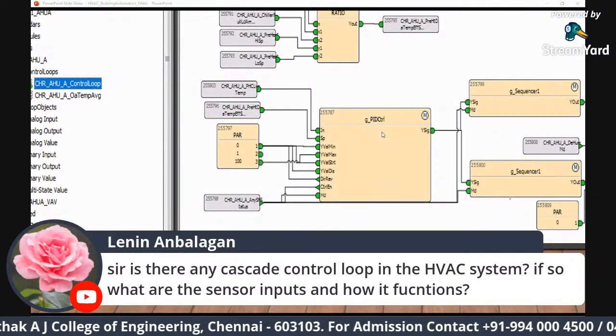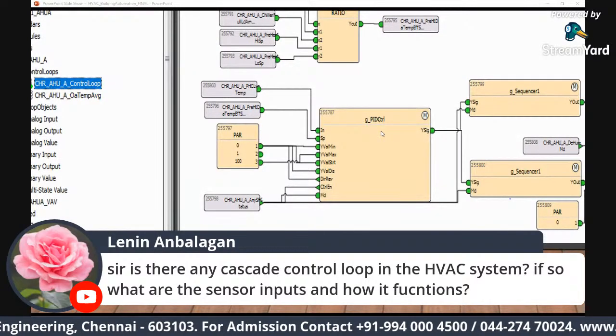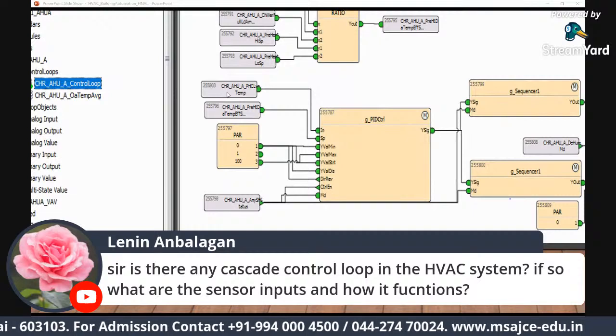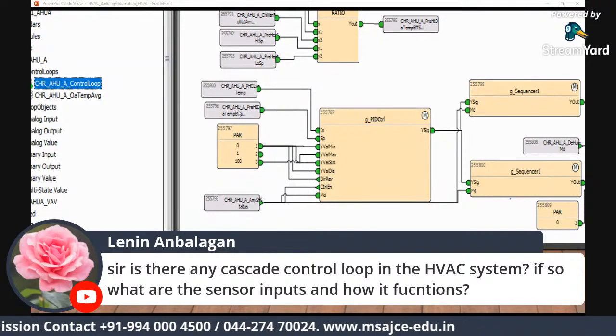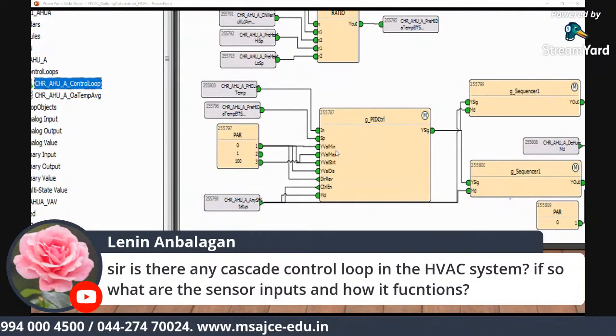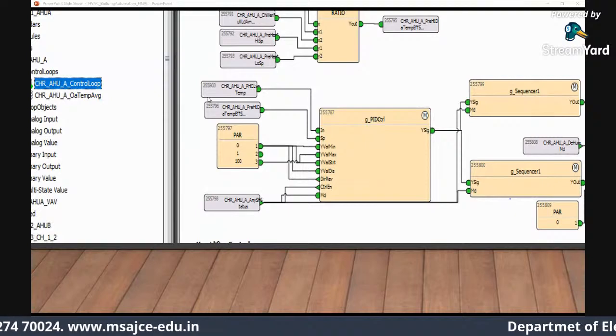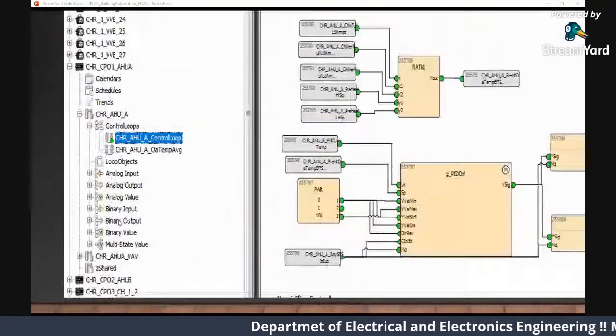People in the control field or E&A background should have known PID control, PID loop control. I'm giving in an input. This is a temperature. This is your set point, and so when to enable the PID, when not to enable. So this is a basic.